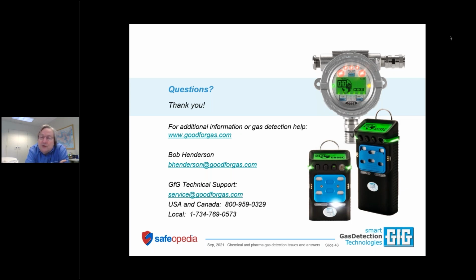So you're not looking for the accuracy of the reading, you're verifying that on that particular day, the sensors respond to gas. So with the docking station, the evaluation includes the accuracy of the reading as well as testing the proper activation of the alarms and the flashing lights and the vibrator and anything else you have built into the instrument. And typically that's going to take for a 4-gas instrument probably 20 to 30 seconds. If you've got a PID in there, then it might take 45 to 60 seconds to get through the daily bump test. But if you are doing a manual qualitative bump test, probably the easiest way to see how long it lasts would be to show you.